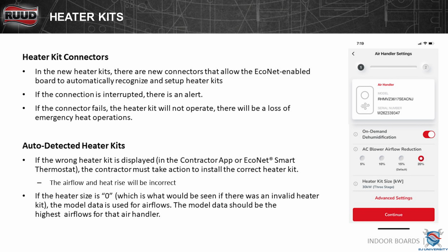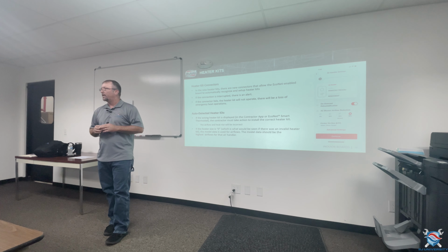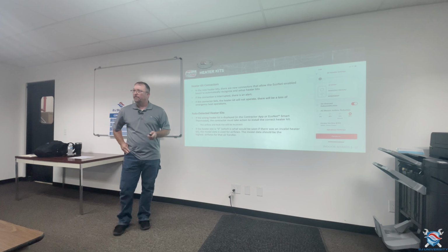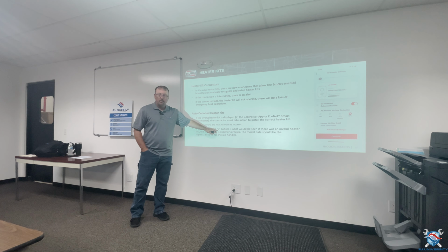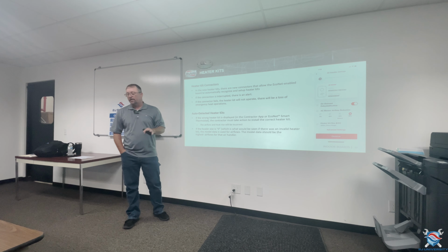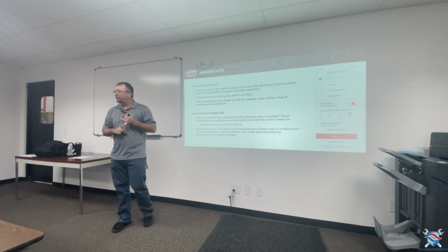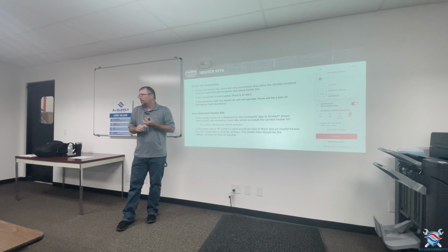Heater kits. One thing that they've changed in the heater kits is on all the new heater kits, they've added a resistor into the heater kit, so it's auto detecting now. So when you have an Econet, or even in the Contractor app, it'll tell you exactly what that is. You don't have to tell it. Before, in the Econet, you always had to tell it, okay, I've got a 10 kW heater kit. Now it's automatically populating. If you ever see a 0 in there, it's basically telling you that it can't find the heater kit, or you just don't have a heater kit.